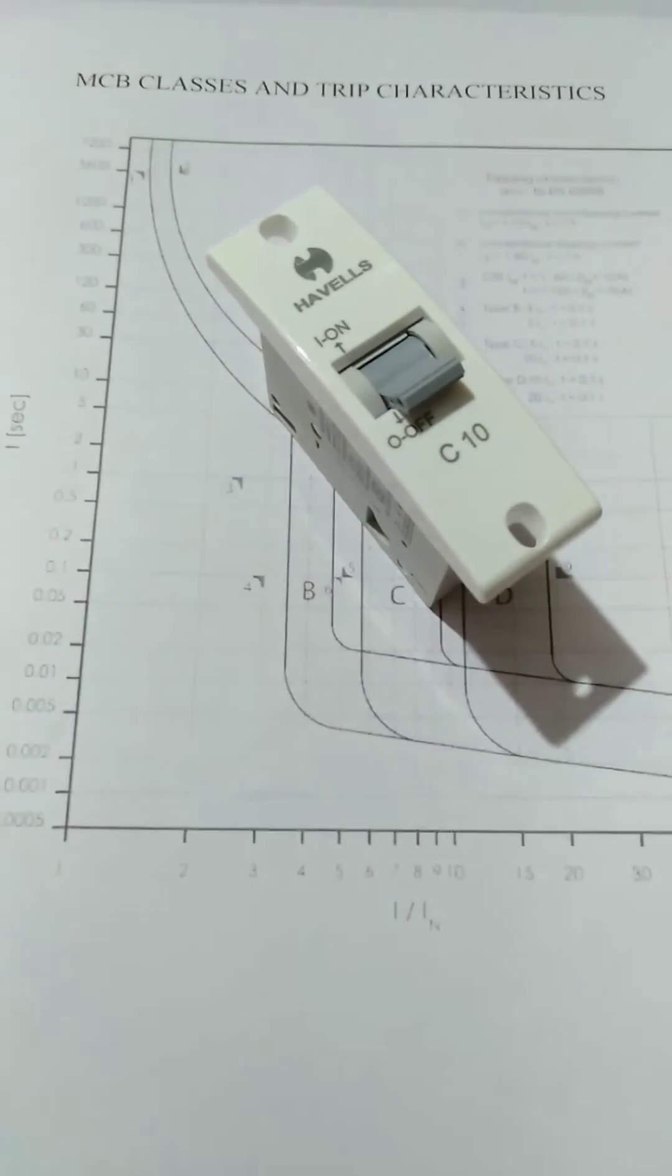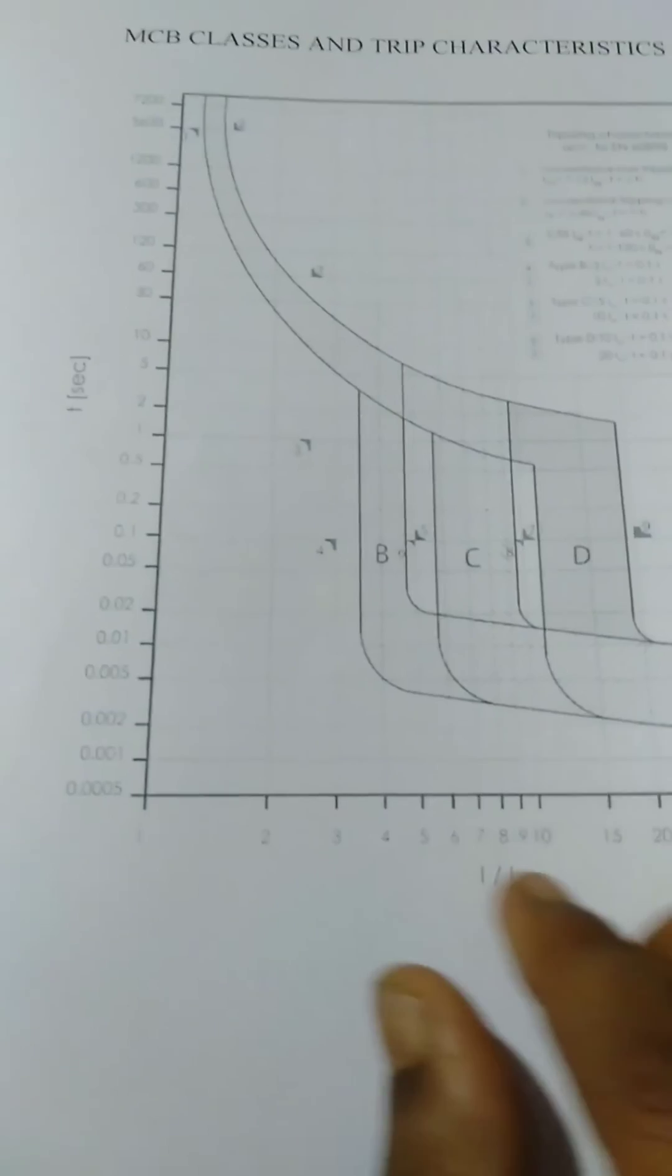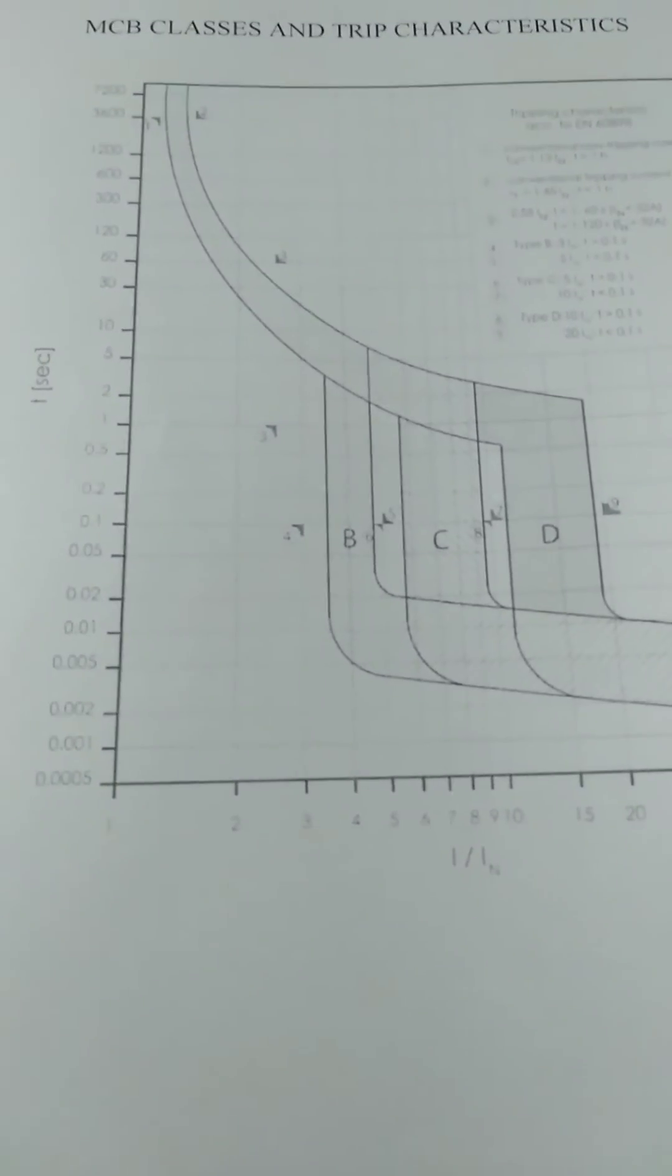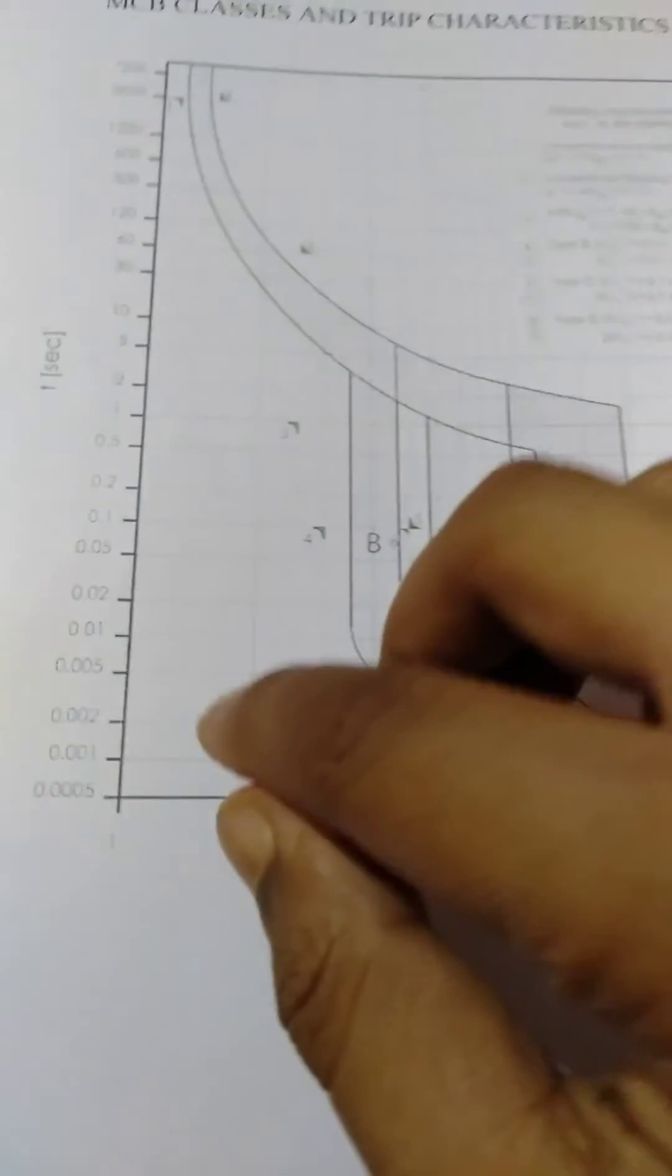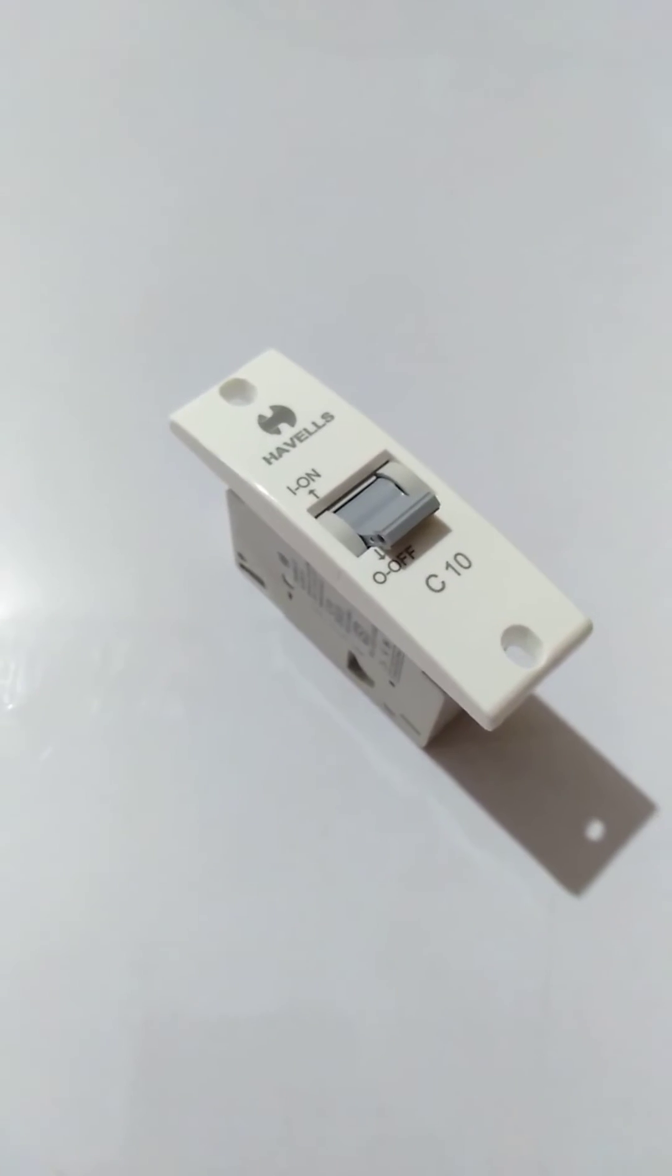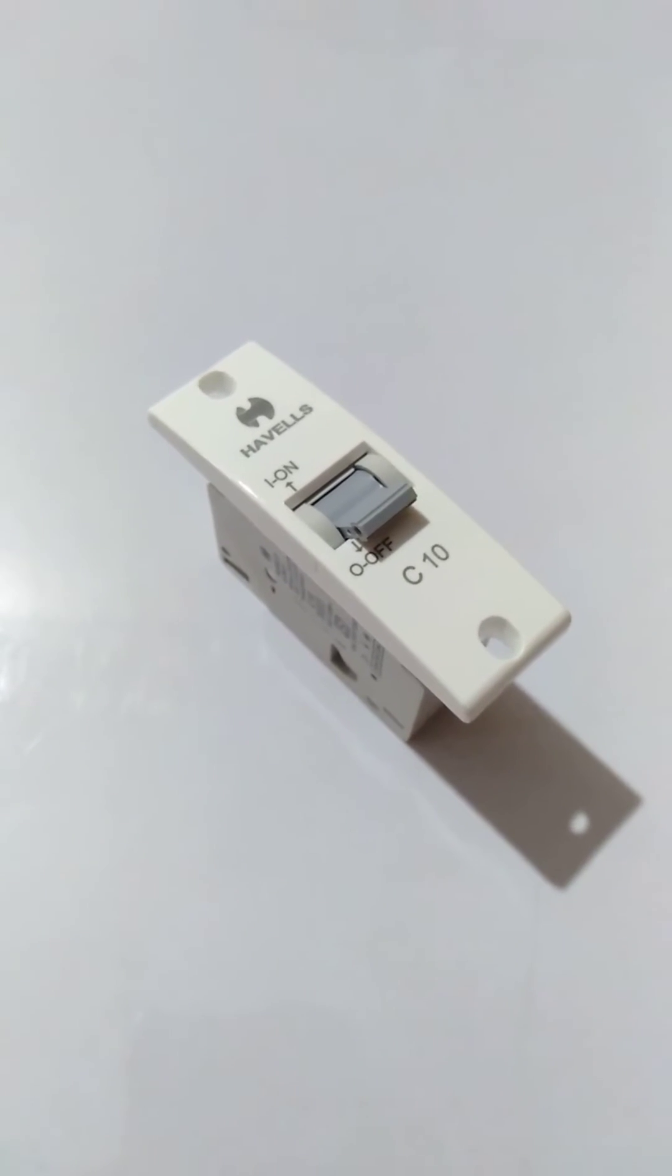For a C class MCB, the graph shows its confirmed trip zone to be around 5 to 10 times the nominal current. For a fault current running twice the nominal current, the trip time is around 30 seconds. Such MCBs are viable only for inductive loads that draw a great deal of starting current.